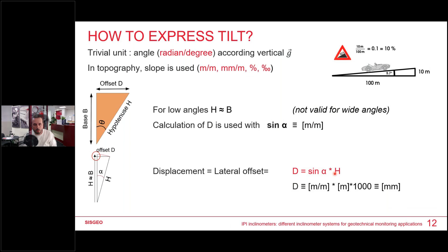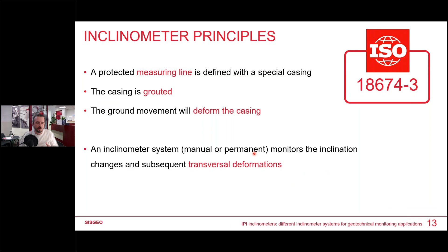So the casing is a tubing. This special casing is defining a measuring line. This measuring line, so the casing, is grouted, so linked to the soil or the structure that you have to monitor. Then the ground movement or the structure movement will deform the casing. So this inclinometer system that you are using, manual or automatic, permanent, monitors the inclination changes of this casing deformed by the ground and subsequent transversal deformation. So the idea is that this casing deforms, and then you get the deformation profile with an inclinometer system. So I remind the principle of the manual device.